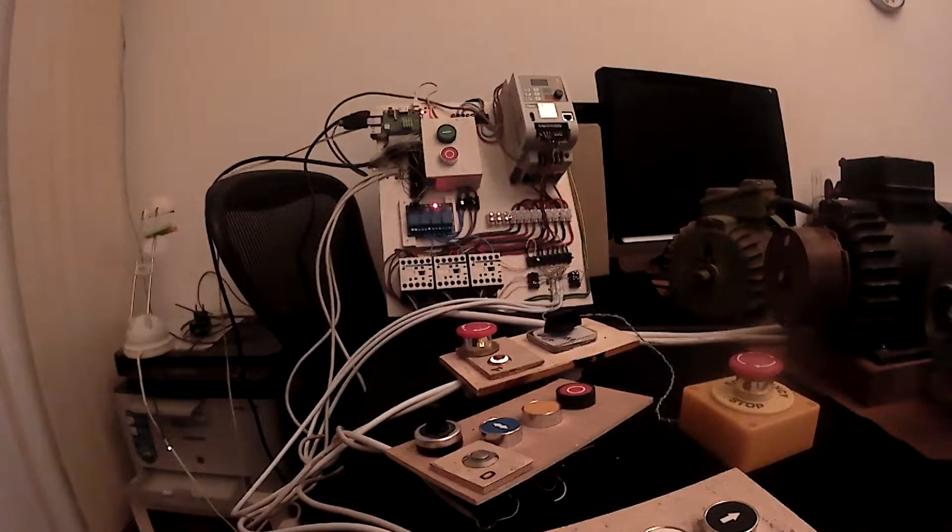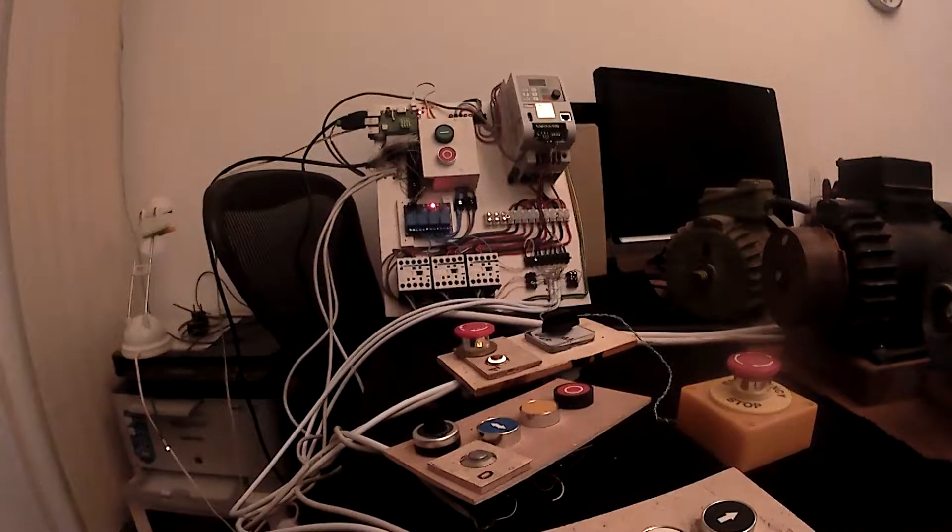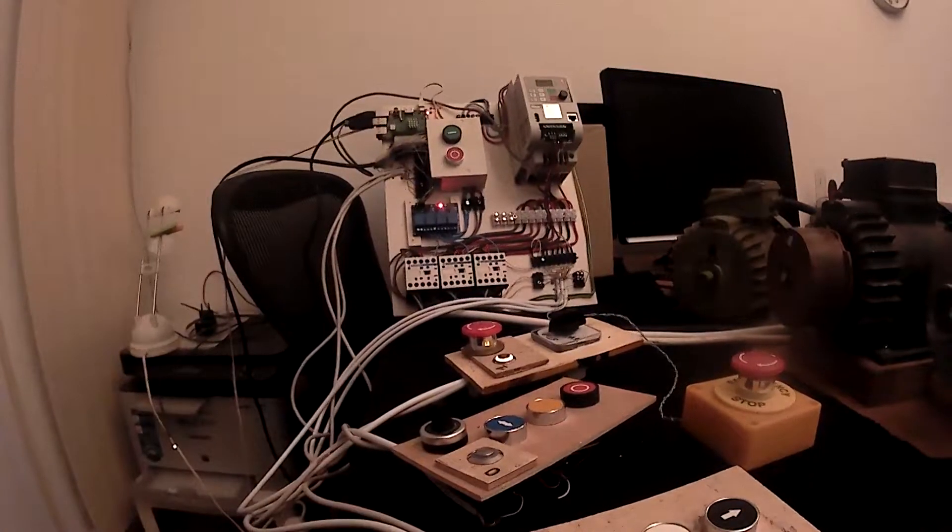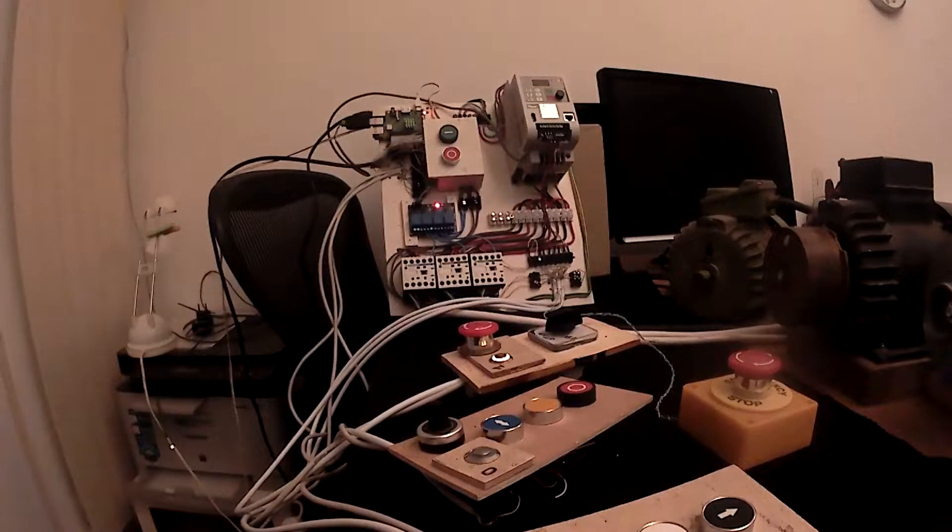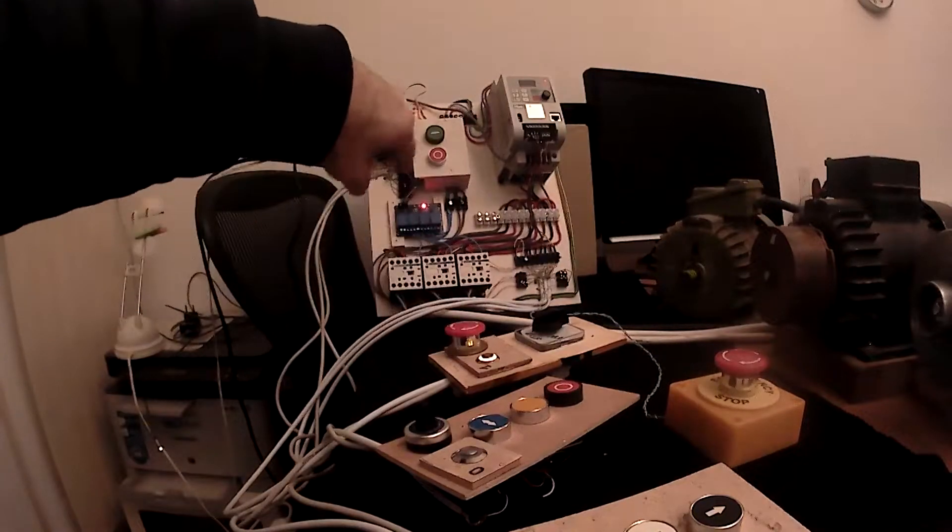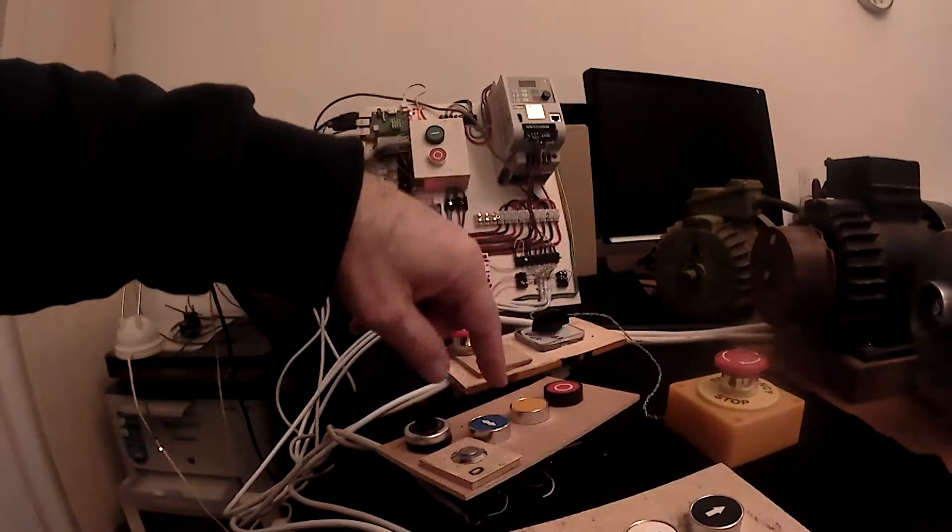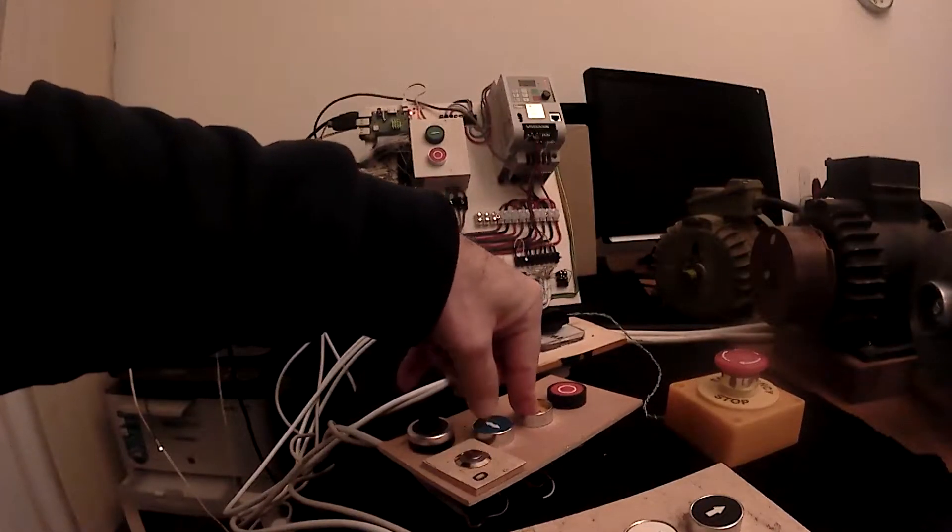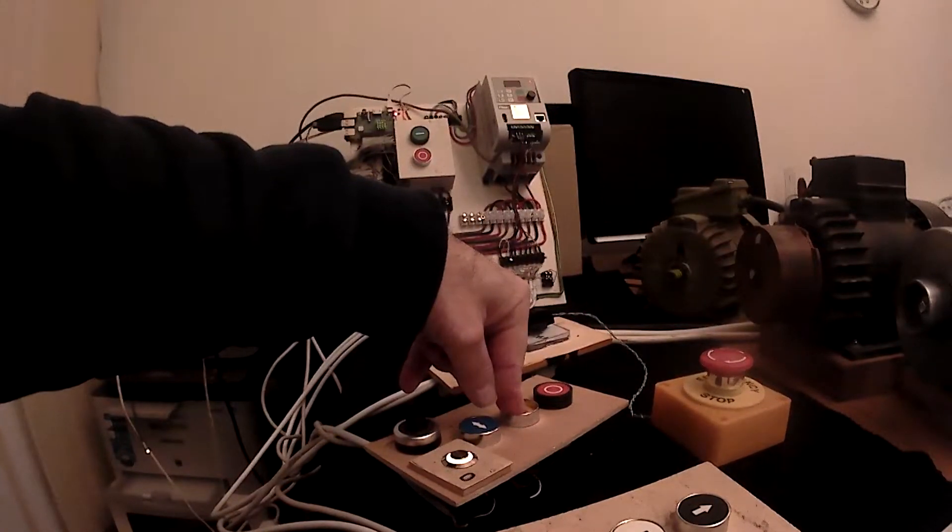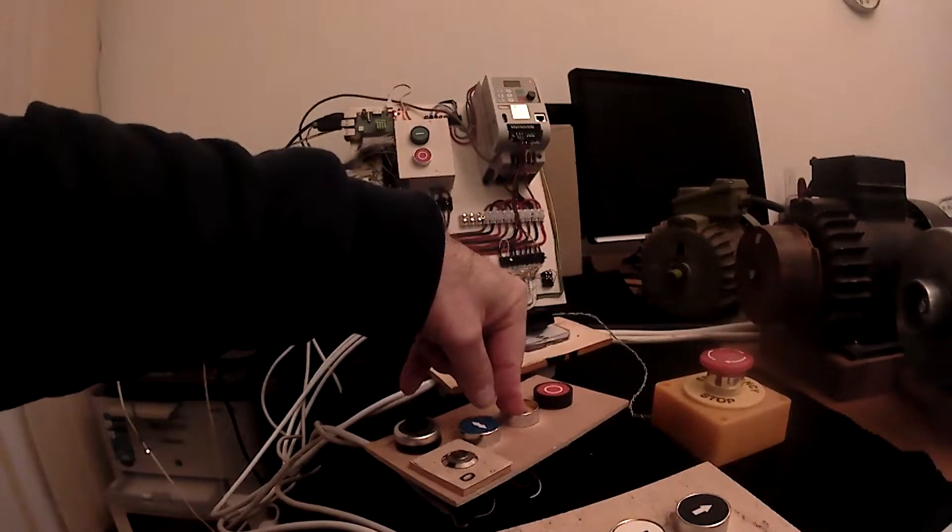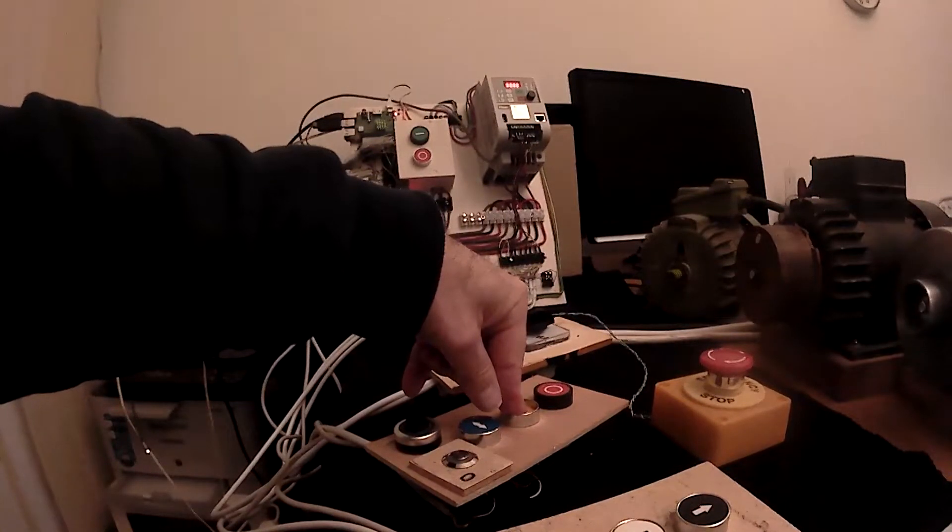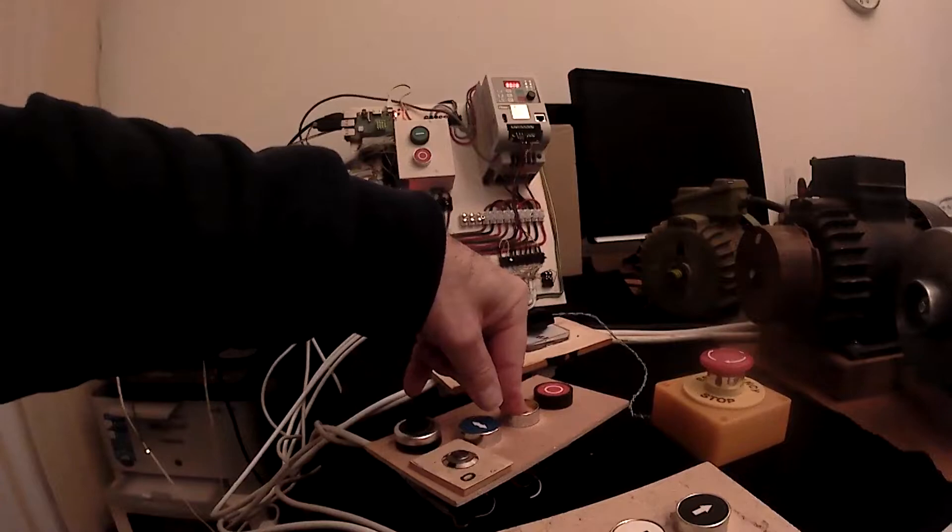The second part of security is to prevent those motors for any spontaneous resume. I mean that if the motor is switched on when you decide to change from a motor to the motor switched on, you may have a spontaneous start from the motors. Obviously, we don't want that. If someone is pushing on the button by accident, or if anything fell on the button, you may have a spontaneous start of the motor.